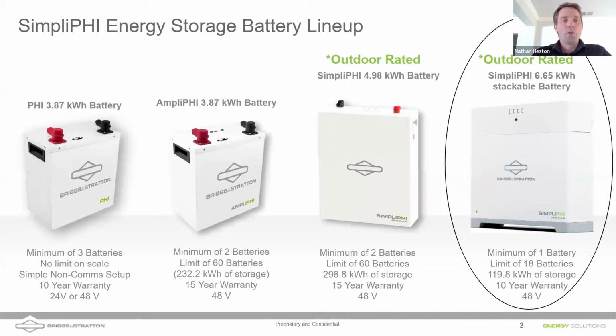We have batteries from our Phi battery, our non-communicating battery, which is a fairly popular option still. It's been a workhorse in the field for many years. We've got many batteries out there outliving their warranty, still providing power for customers from our early days. We've introduced a few years ago the SimpliPhi battery that you see, and that's a communicating battery. Of course, it has closed loop communications with Sol-Ark inverters. And then more recently, we introduced the 4.9 kilowatt hour outdoor rated battery. And it has a similar BMS communication protocol that also matches up with Sol-Ark.